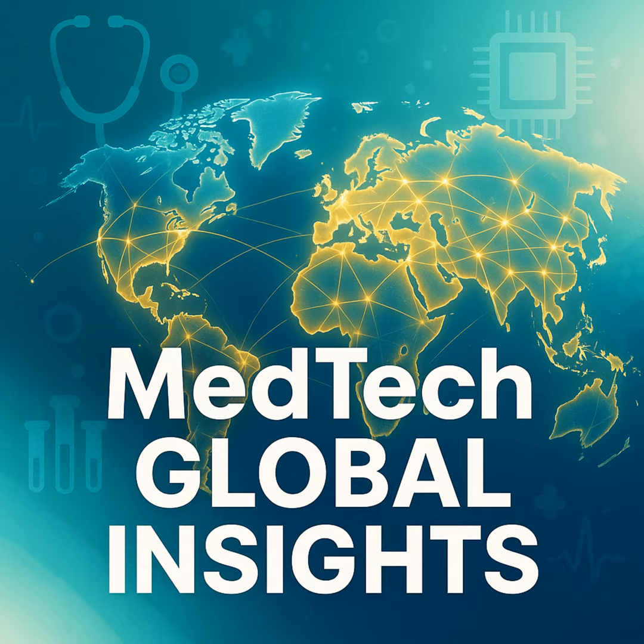Post-market surveillance, or PMS, is also not a static process for AI. You must have a proactive plan to monitor the device's performance in the real world. This is especially critical if the algorithm has the capacity to learn or adapt over time.